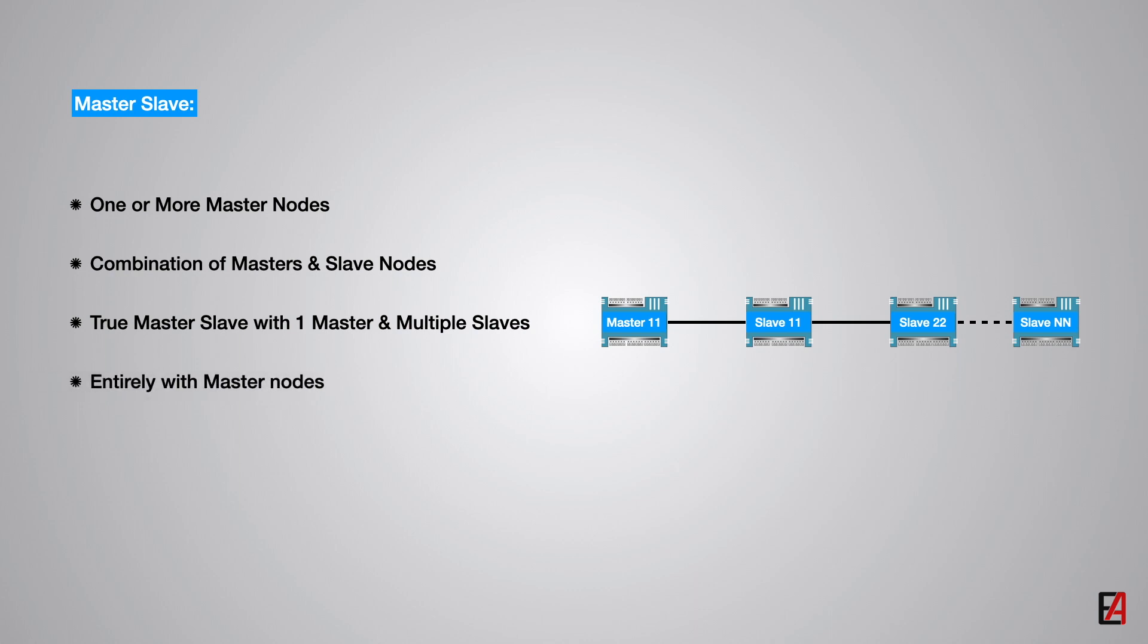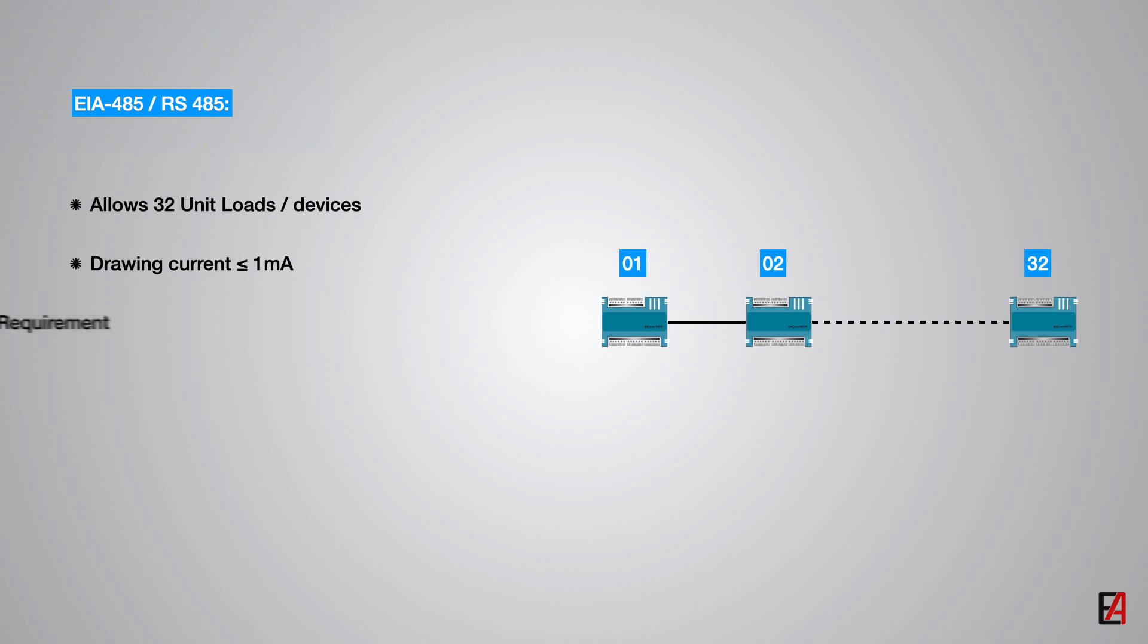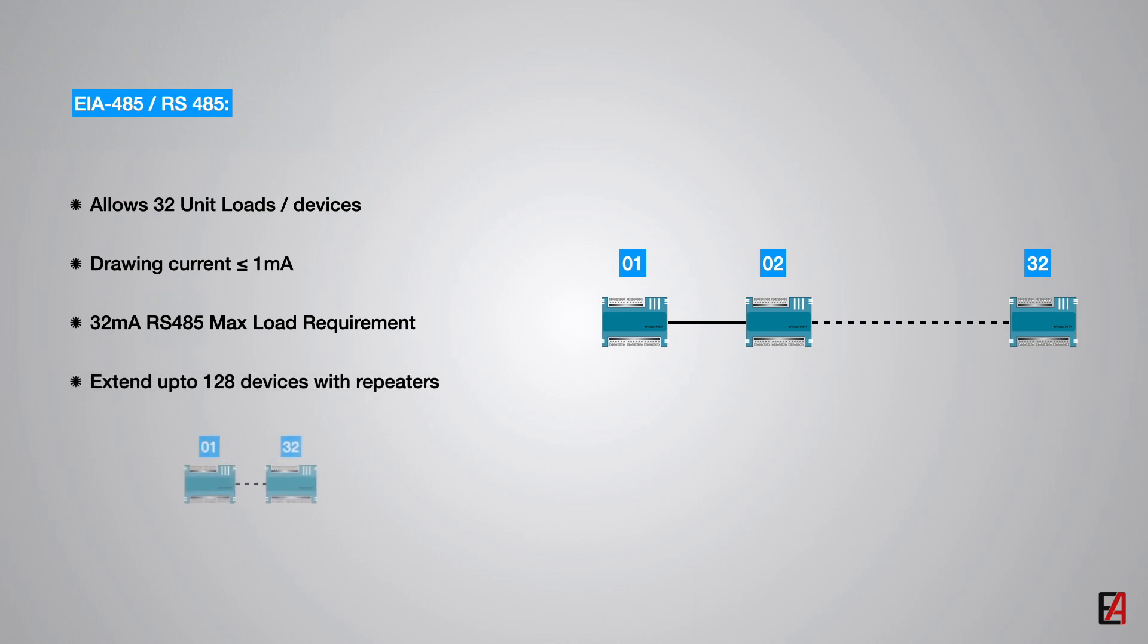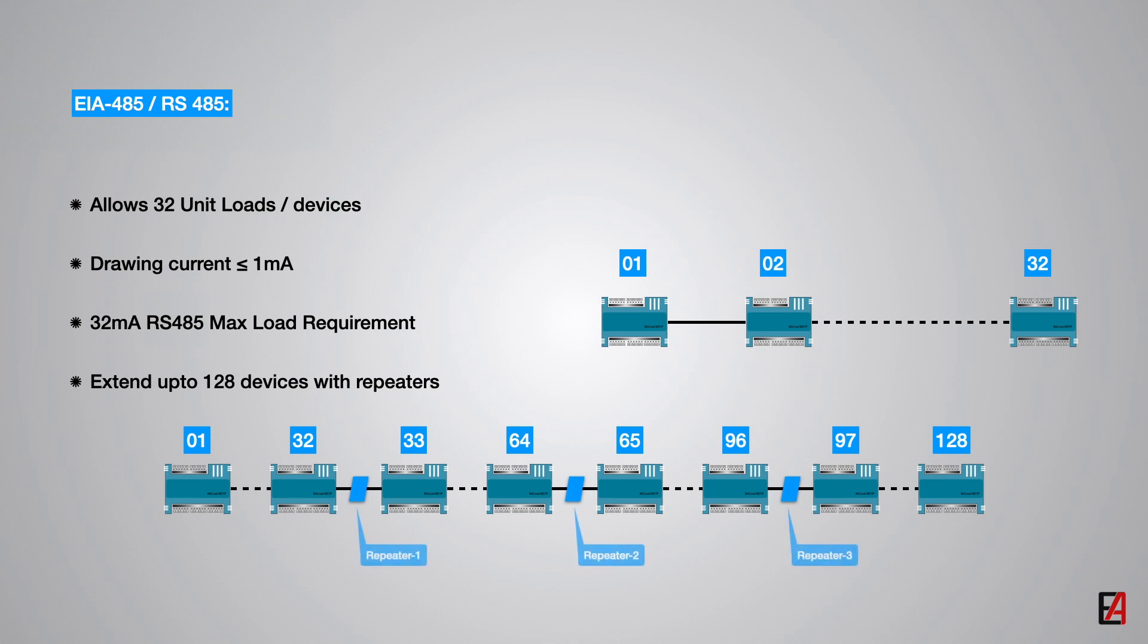Now we will see the RS-485 standard requirements for devices connected on the MSTP network. The RS-485 standard allows up to 32 devices with 1 unit load per device to be connected on a single network. The load from each device must be less than or equal to 1 mA drawing current. The maximum load current requirement of RS-485 is 32 mA on a bus. The MSTP network allows up to 128 devices to be installed on a single network with one or more repeaters.